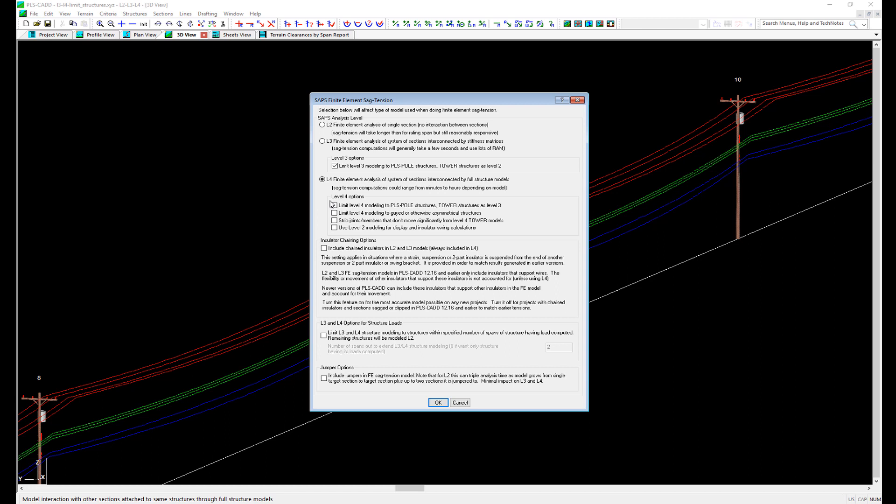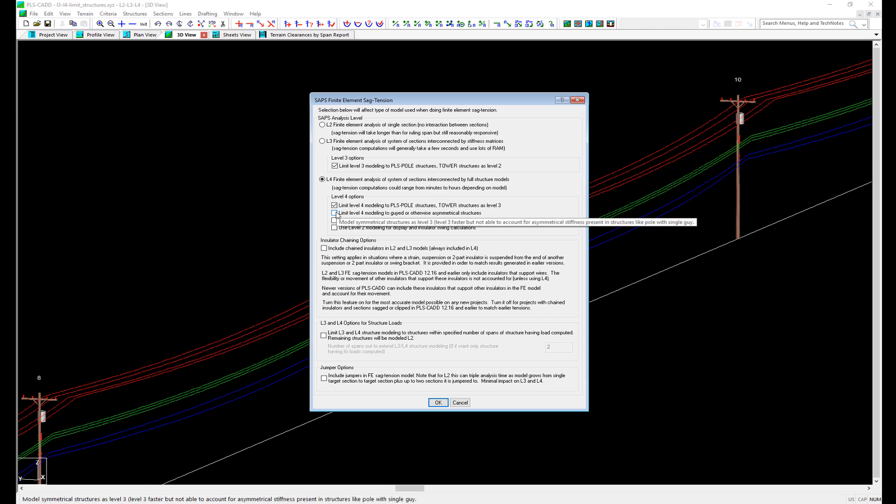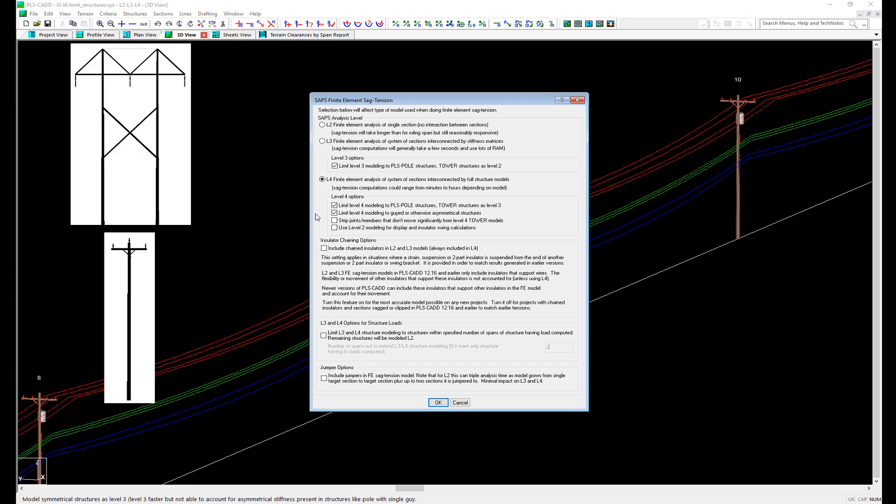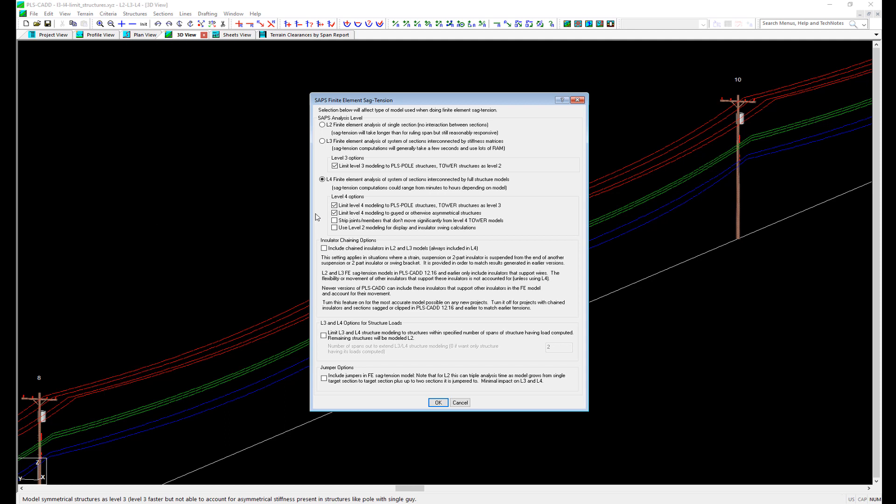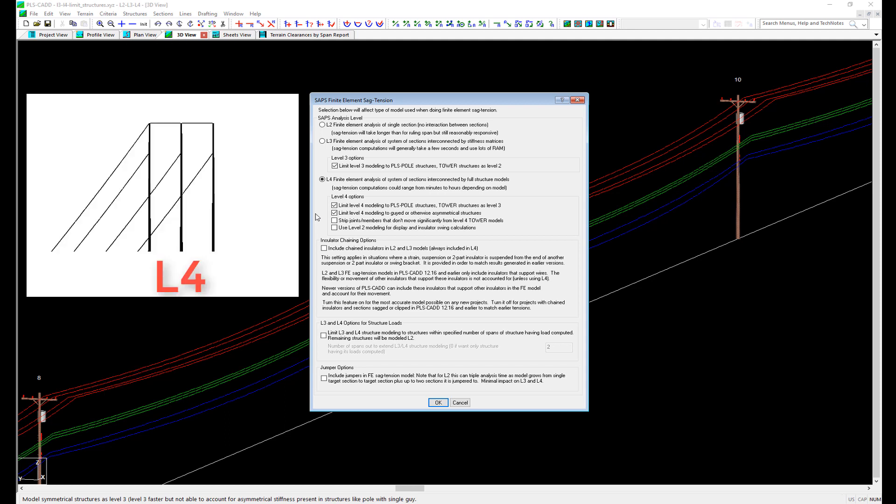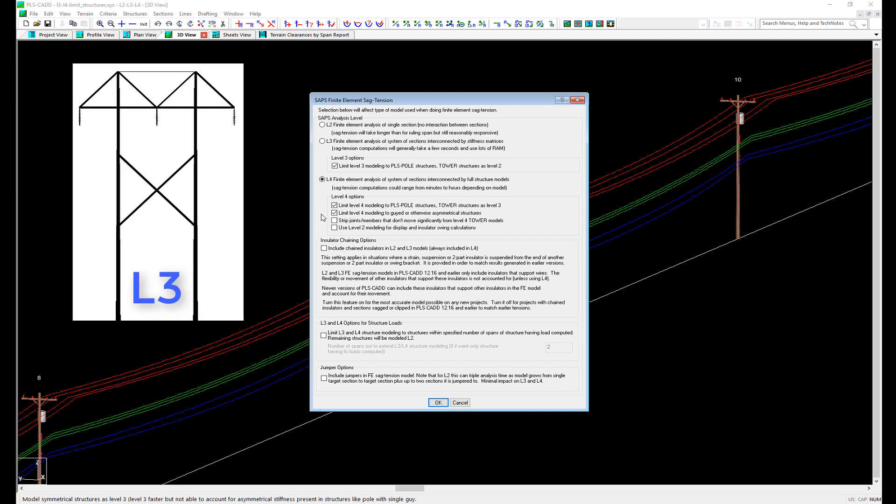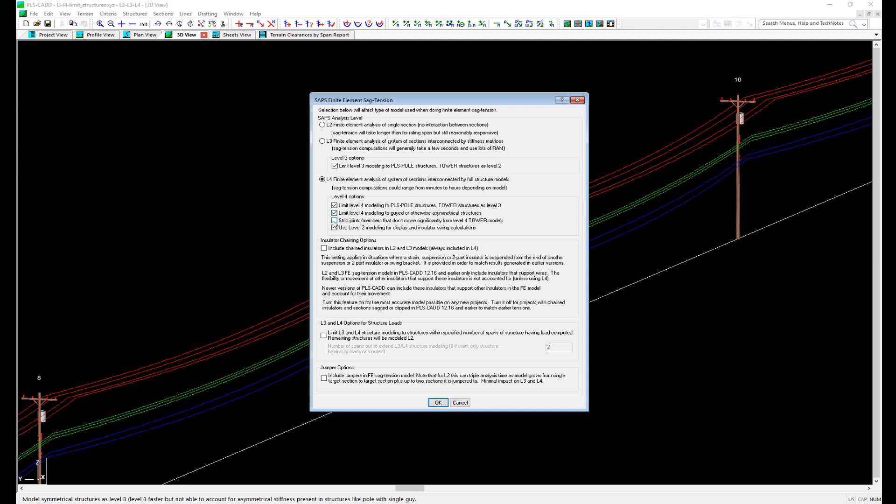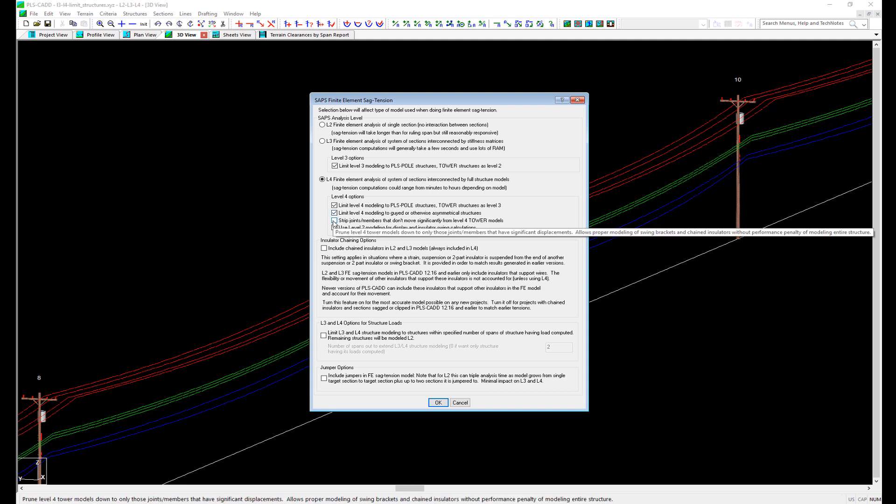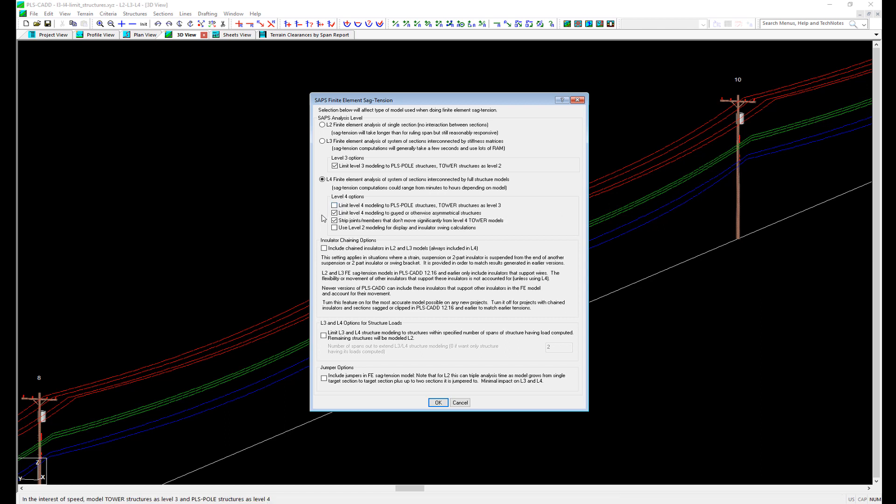L4 analysis also has some options to make it run faster. The first option is to use L4 on PLS-POLE structures only and limit tower structures to L3. Just like the option in L3, this is limiting tower structures to a lower level of analysis because they are typically very rigid and do not deflect heavily. The next option is to limit L4 to just structures that have guy wires or asymmetric stiffness. With this option, structures that do not have guys or are symmetrical can be analyzed in L3. These options can give you the best of both worlds between L3 and L4, with the accuracy of L4 for structures that need it and the speed of L3 for acceptable structures. The third option in L4 is to strip or remove joints and members from tower structures that do not deflect a lot. This option can simplify tower structures being L4 analyzed to speed up the analysis, and should only be used if you are not choosing the first option to make tower structures analyzed in L3.